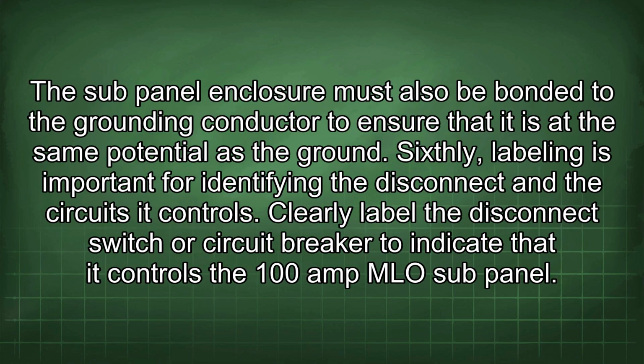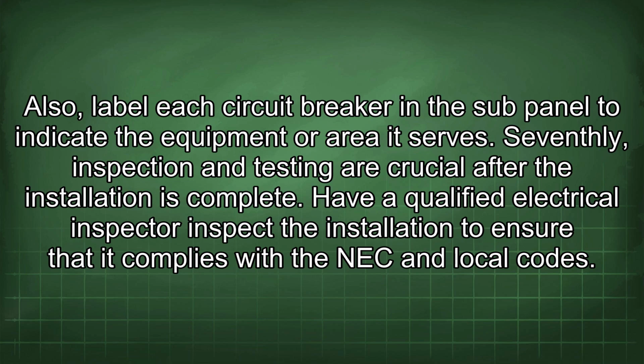The sub-panel enclosure must also be bonded to the grounding conductor to ensure that it is at the same potential as the ground. Sixthly, labeling is important for identifying the disconnect and the circuits it controls. Clearly label the disconnect switch or circuit breaker to indicate that it controls the 100 amp MLO sub-panel. Also, label each circuit breaker in the sub-panel to indicate the equipment or area it serves.